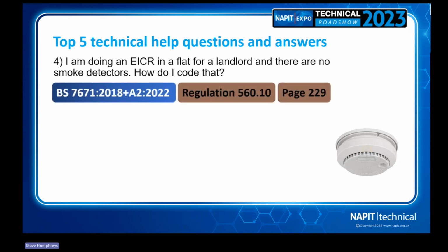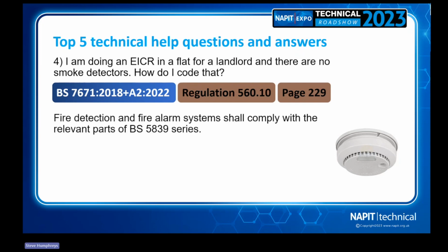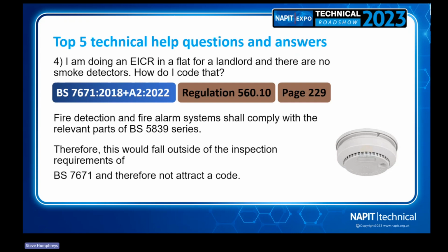Now, actually, this is an interesting answer, because if we look at Regulation 560.10 on page 229, it says this: fire detection and fire alarm systems shall comply with the relevant parts of the BS 5839 series. So that's the British Standard for the actual equipment. Therefore, it would seem common sense that this would fall outside of the inspection requirements of BS 7671 and therefore would not attract a code in that circumstance. But, however, there's always a but.